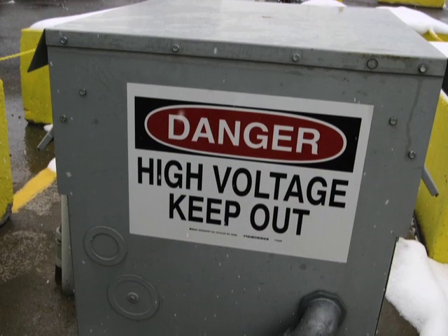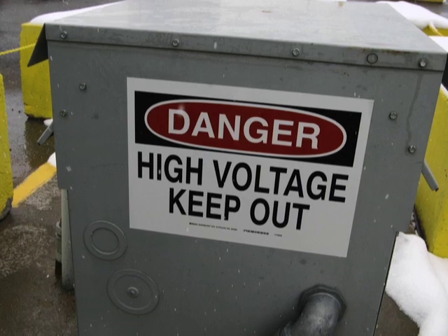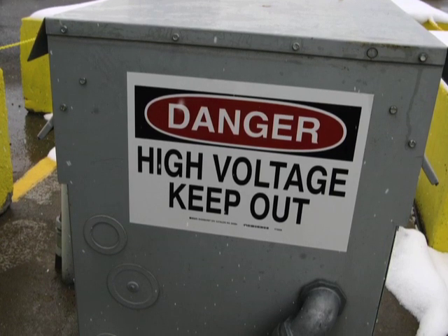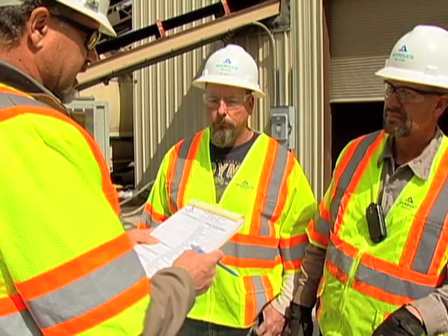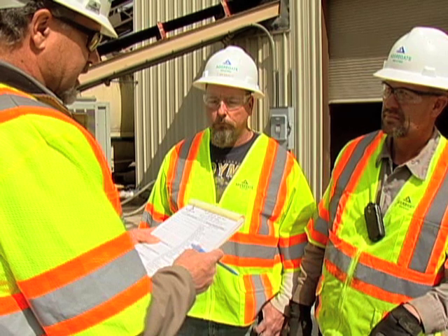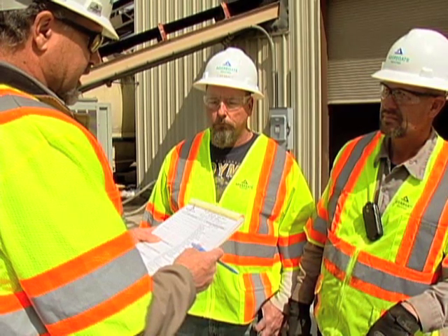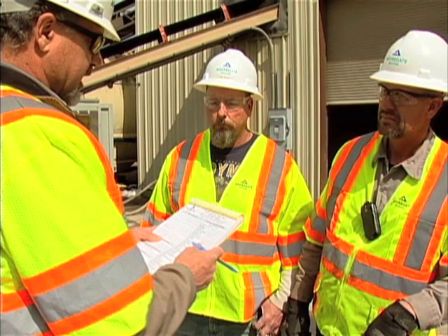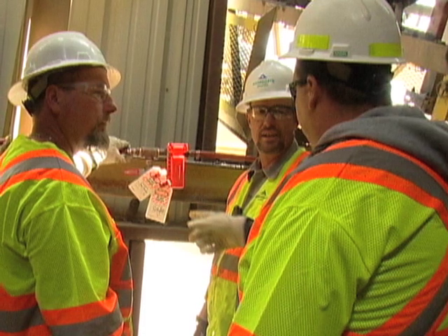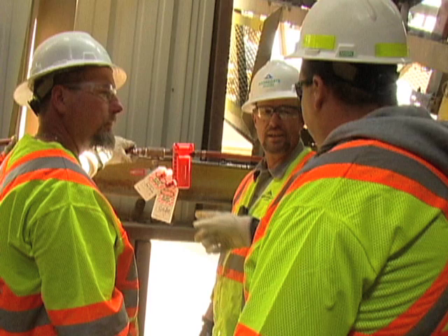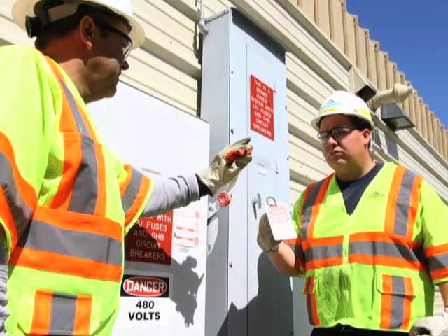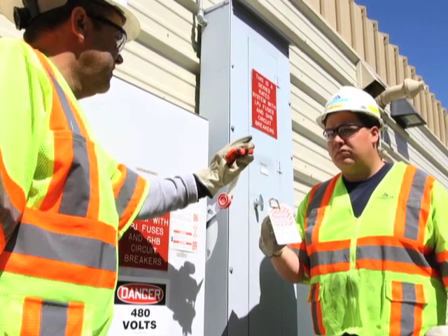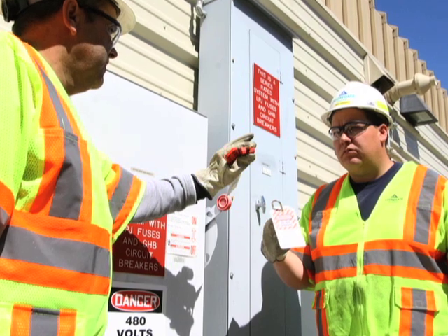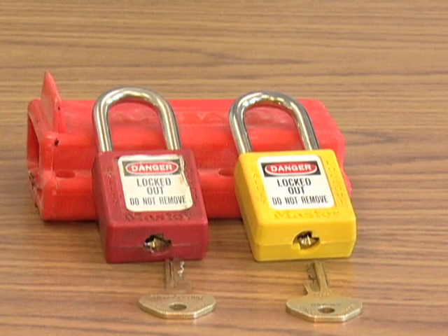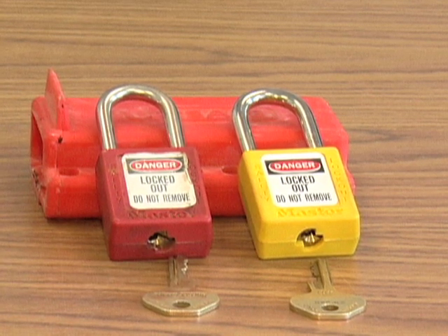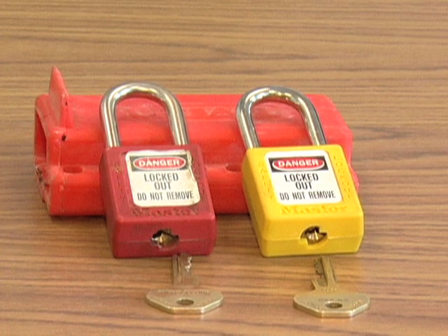Number 6, not correctly and completely identifying all energy sources when lockout, tagout, and tryout are required for a procedure. Number 7, failure to have an annual review of all hazardous energy sources and lockout, tagout, and tryout procedures. New energy sources may have been added. Energy source labels need to be in place. Number 8, failure to adequately train employees in what is maintenance and what are simply minor routine tool changes. Number 9, oversight. Just incorrectly assuming that every lockout, tagout, and tryout procedure is always going to be the same. Number 10, duplicate keys available to other workers, which enable non-authorized employees to override a lockout, tagout, and tryout procedure.